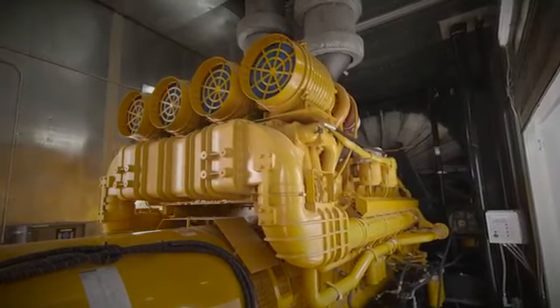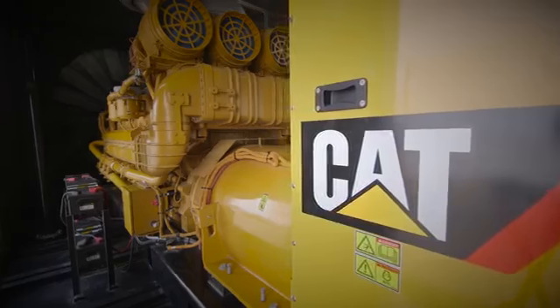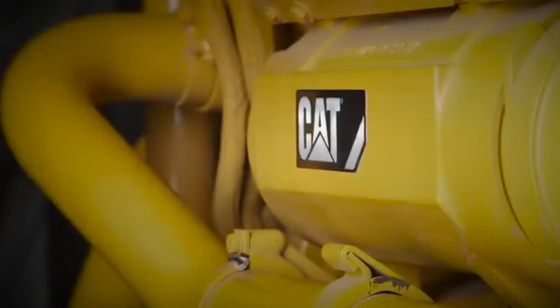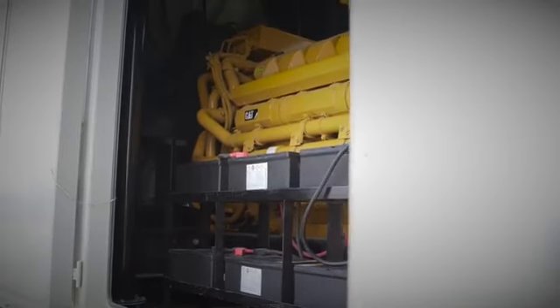These are CAT C-175 3-megawatt capacity units used for backup power for the city of Johnson. We would need to use the generators during ice storms, if we lose our power lines, anything that interrupts service. The CAT C-175 3-megawatt Tier 4 unit is a very superior piece of equipment. It meets all of the Tier 4 emissions regulations from the factory, which gives us a competitive edge, and it also allows a size range that the competition currently does not offer.